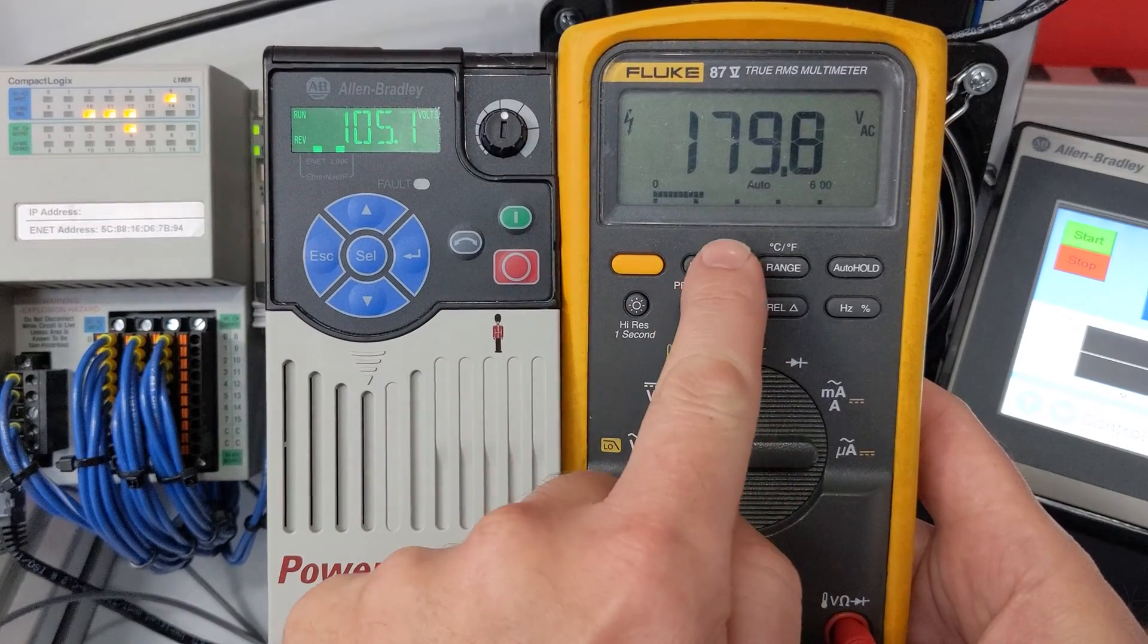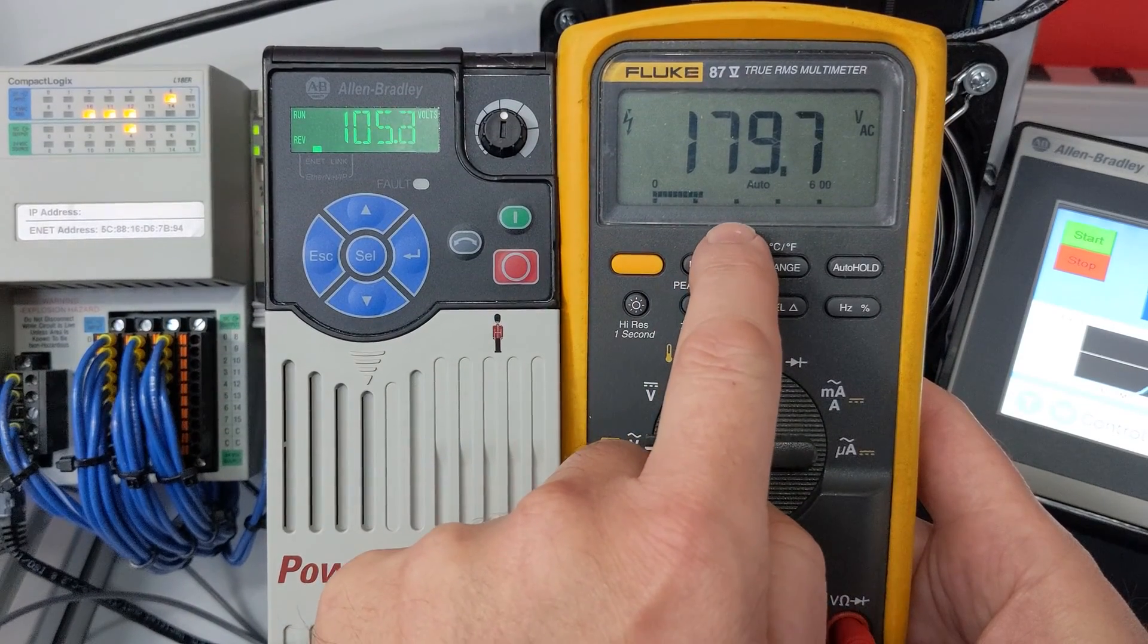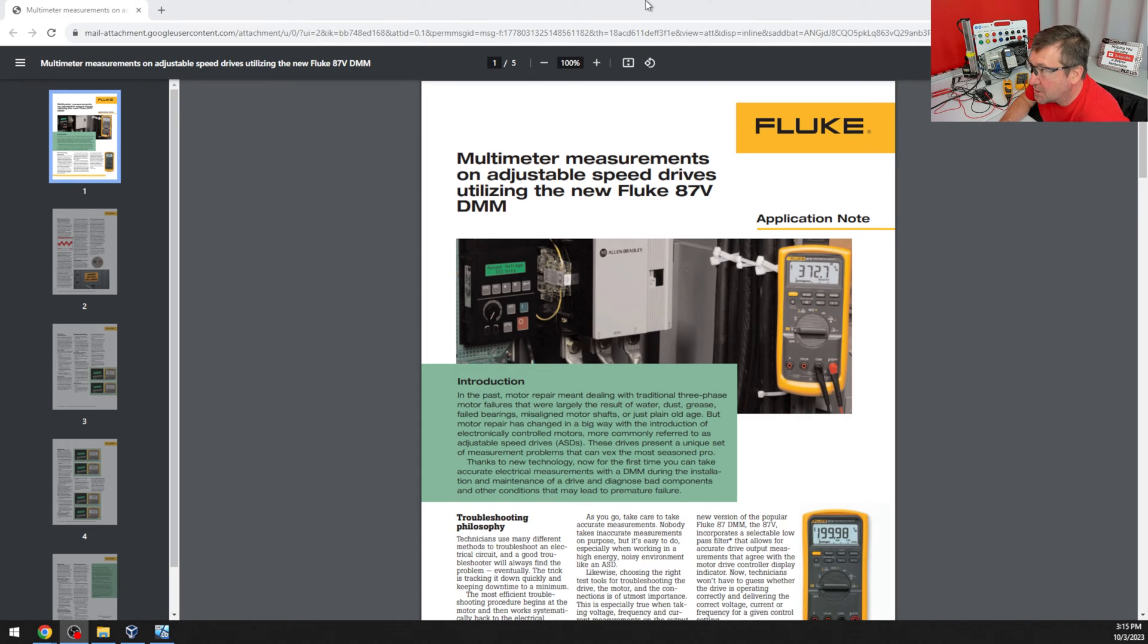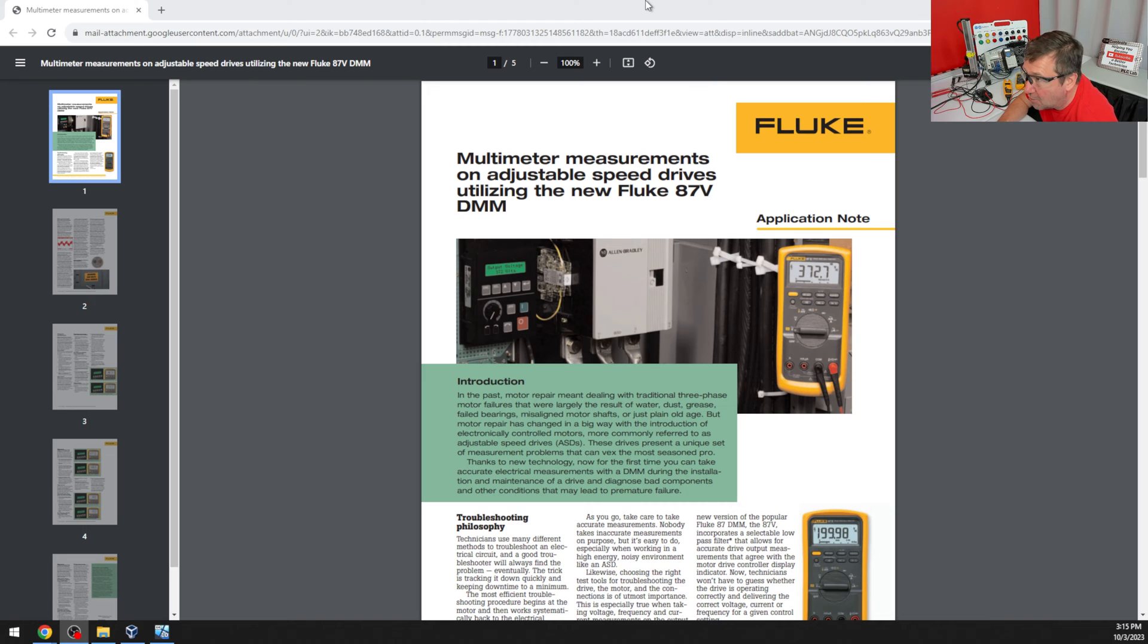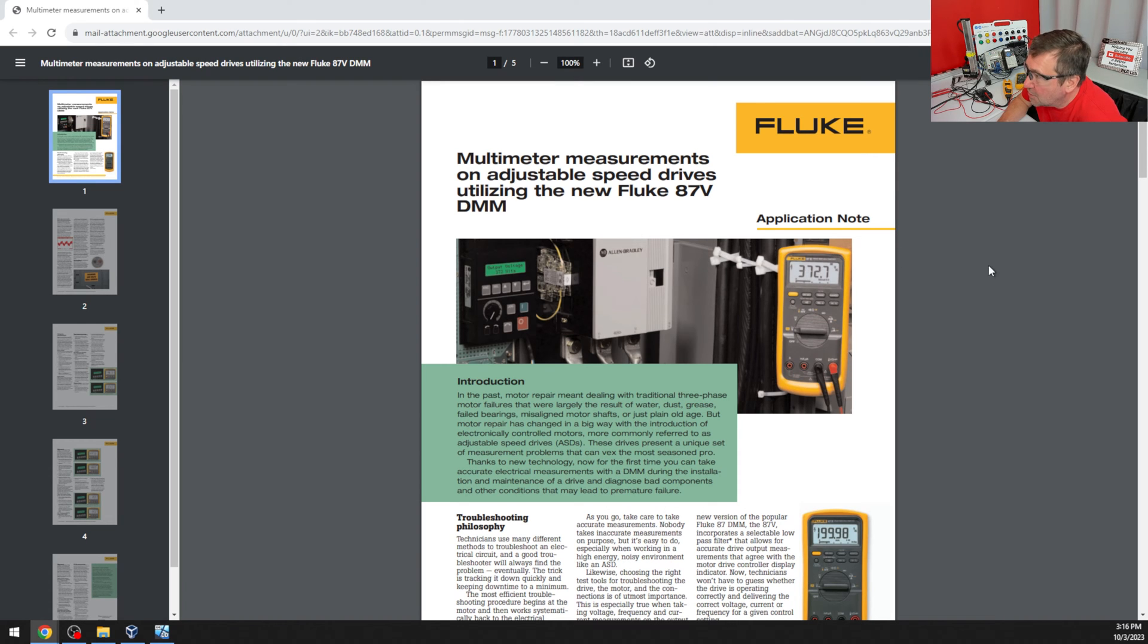And initially, I was confused on the 87V because it's showing 179 volt AC. And when I reached out to Fluke to ask them about the discrepancy between the 87V and what the Allen Bradley PowerFlex 525 was saying, they pointed me to this document that talks about the low pass filter that they use to measure the VFD output.